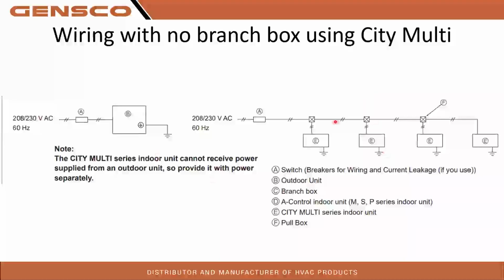You will need to have at least 2 circuits on this system for high volt, one feeding your heat pump and one for your indoor equipment. One thing I'd like to point out as well is if you do have a branch box that is powered separate from the heat pump, or you're doing City Multi like this, where your indoor equipment is powered separate from the heat pump, anytime you have separate power supplies, indoor disconnect switches, anything like that, those indoor units need to be turned on before the heat pump turns on.